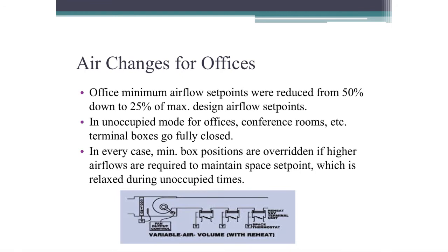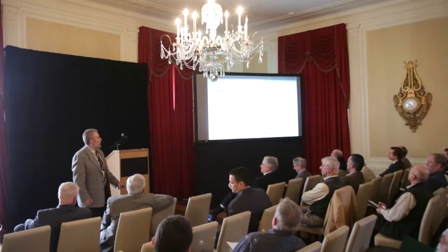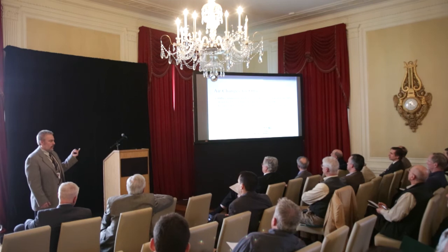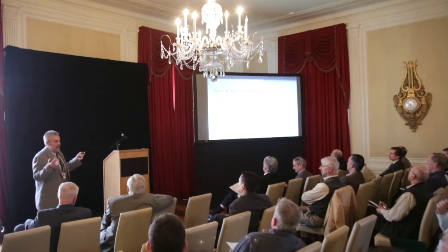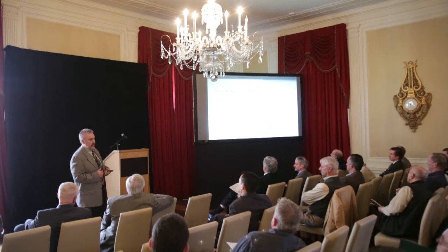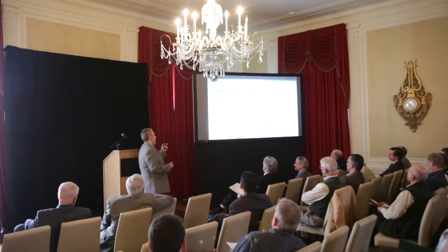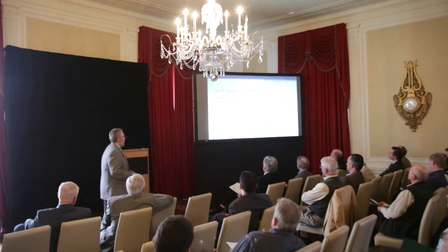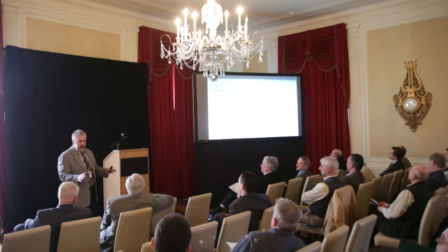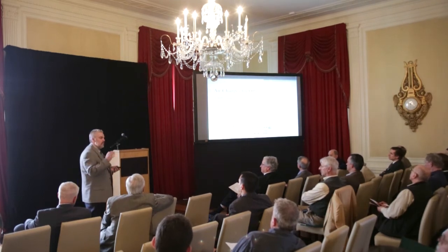Air changes for offices, there are still, like we said, a lot of offices even in labs. Air changes typically, engineers are lazy, let's be honest. They say, okay, the VAV system, the minimum is 50% of the maximum. It's easy to divide by 2, right? So you're going to divide that in half, and you're going to come up with your minimum. Well, 50%, like these guys were saying, is still way too much. If we're providing 6 air changes just for sensible cooling in the space, it's too much air. We do it in offices with 2 air changes. So it didn't make any sense. We went back and revisited them. We lowered the minimums again, came up with an appropriate one. Had to maintain the pressure relationship. I say that again because that's kind of key. You have to make sure that you do that.